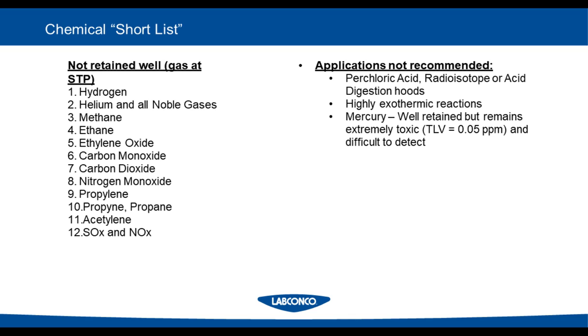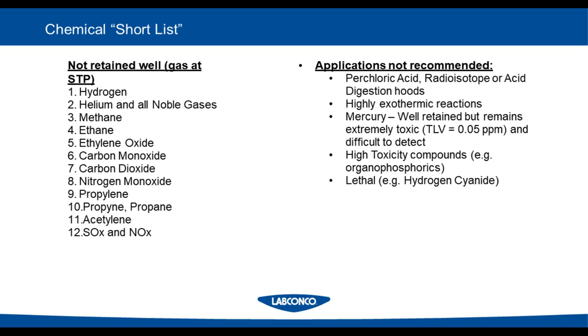Mercury, not commonly used anymore, thankfully. We can capture it really well. The problem is we can't detect it, so we put that on the no-go list, not down at the TLV level required anyhow. And then anything that's high toxicity or basically immediately lethal, those would not be used in a filtered fume hood.